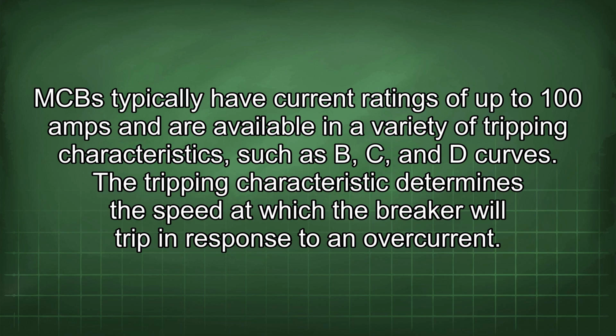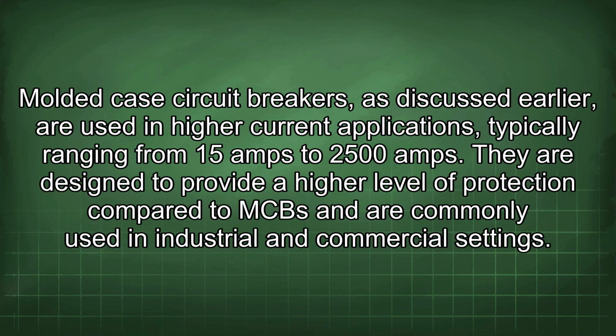MCBs typically have current ratings of up to 100 amps and are available in a variety of tripping characteristics such as B, C, and D curves. The tripping characteristic determines the speed at which the breaker will trip in response to an overcurrent.